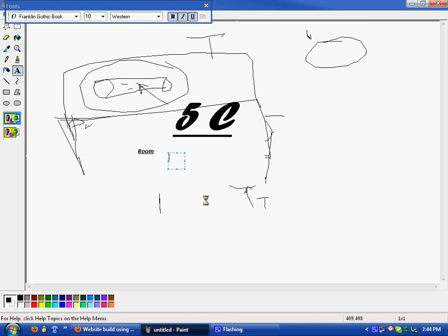The fluid inside the tube will start taking heat from the room. Get it? It will continuously take up heat until its temperature reaches its boiling temperature, that is here 5 degrees centigrade. When it reaches 5 degrees centigrade, it will evaporate. Let's make a cycle like this.